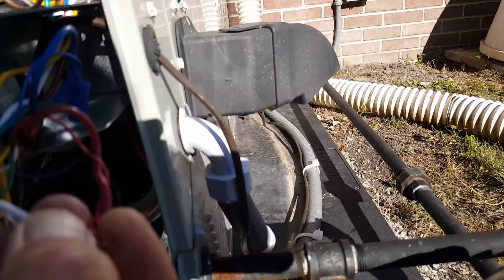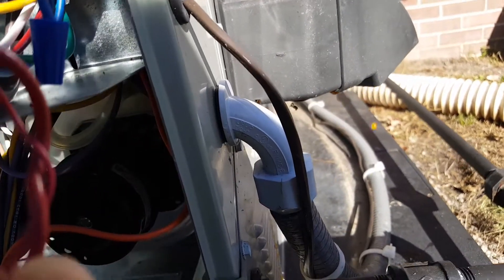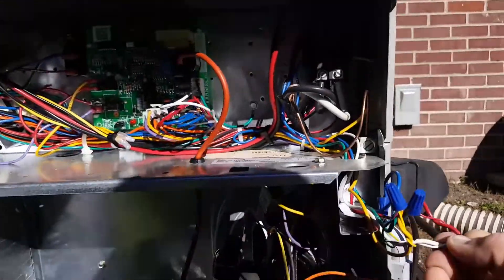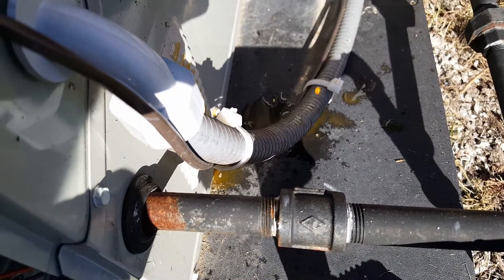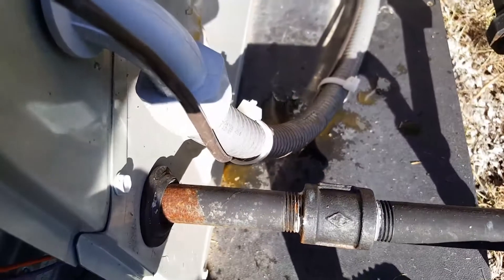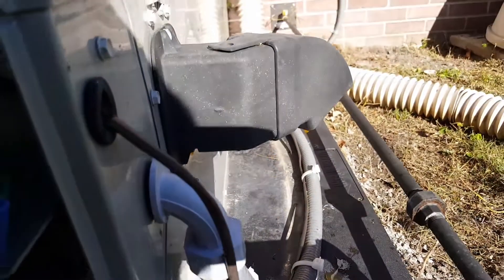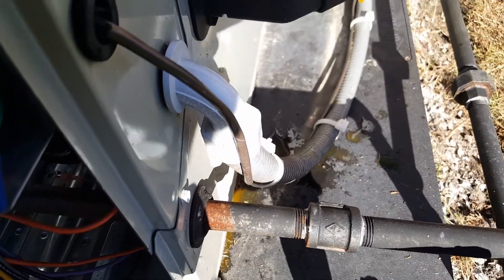Water's spitting out. This unit was not included in the recall by Trane. I don't know why, but it has the same problem as the 4YCY that is included in the recall.